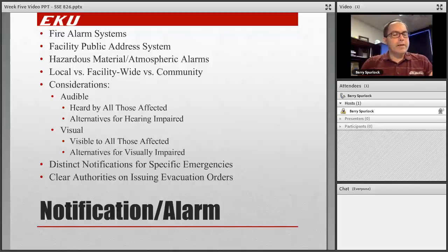One of the things I've run into personally is utilizing that public address in certain areas of our facility because of the ambient noise, and we had many hearing conservation areas. Even if you're on the public address system, you sound like Charlie Brown's teacher. So you have to think about, can the people hear the message? Is it audible, and is it understandable?